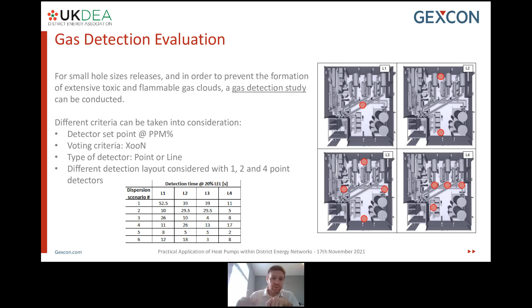So the conclusion that we would have for this case study is that the ventilation system shows poor performance in several areas of the energy center, resulting in the potential accumulation of gas in those areas. This would lead to the redesign of the ventilation system or alterations to the detection system, in order to perform better upon a release of gas.